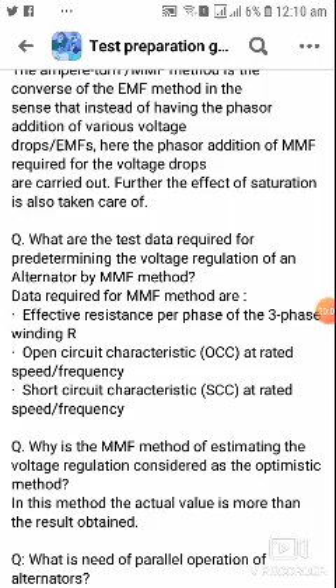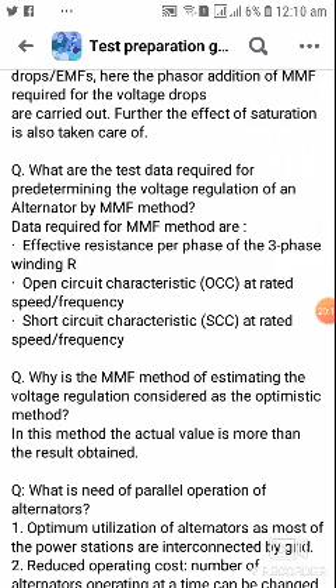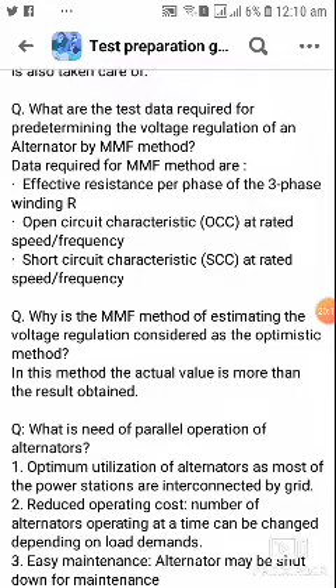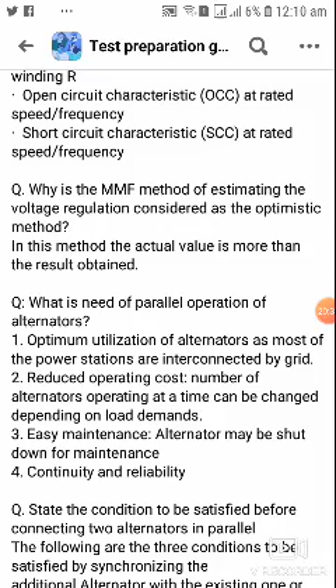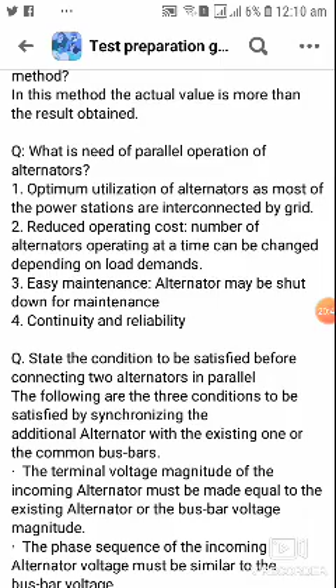Question number 36, what are the test data required for predetermining the voltage regulation of an alternator by the MMF method? The effective resistance per phase of the three-phase winding, open circuit characteristics OCC at rated speed or frequency, and short circuit characteristics SCC at rated speed or frequency. Question number 36, why is the MMF method of estimating the voltage regulation considered the optimistic method? In this method, the actual value is more than the result.